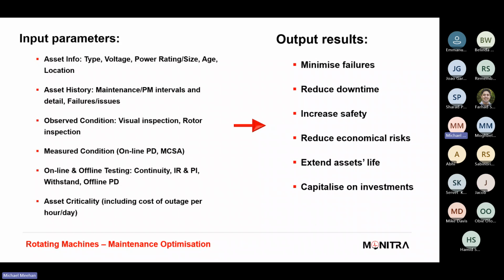So when you do your asset management plans, there's a lot of factors that you take into consideration when you're looking at risk and planning what type of maintenance strategy best fits the motor, its machine, its environment, and everything else. And where you can, you want as much condition data as possible, on and offline. It all helps to correlate the motor condition. The preference to use online is obviously a big advantage. Once you've got as much information as you can from the online, you can then extend any offline outages by a year or two potentially.